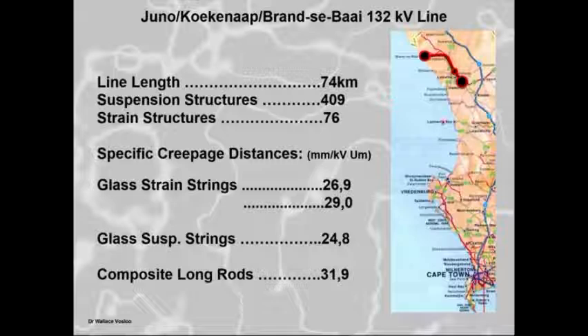Now, normally in this coast environment, we get salt fogs coming in quite a lot, and so we get salt fog banks moving in onto this coastline. So we do have salt fog pollution, and then obviously we get strong winds which are coming down here, and so we get a lot of pre-deposit type pollution, but also instantaneous salt fog pollution. So pollution is an issue here. The rainfall is very low, under 250 millimeters per year. So we don't have a lot of natural washing taking place here. And we get these winds coming from the coast inland and going out, in and out like this, depositing pollution from the coastline as well. And we've got a lot of sands, because this is a very harsh environment, but very rich and wealthy in minerals and so on. So obviously a lot of mining activity.